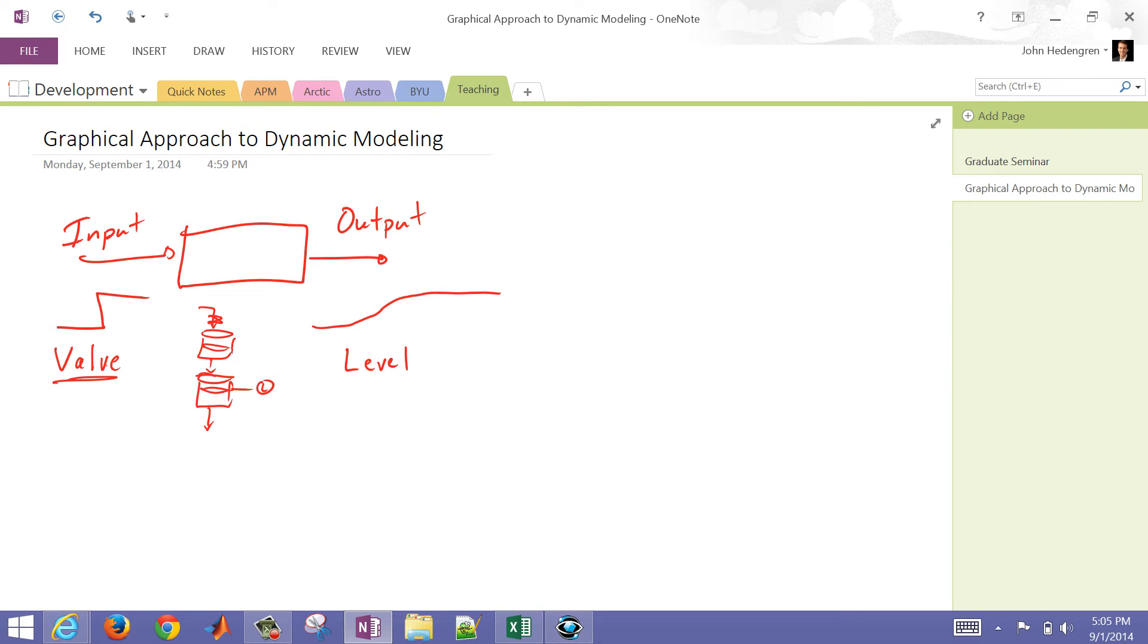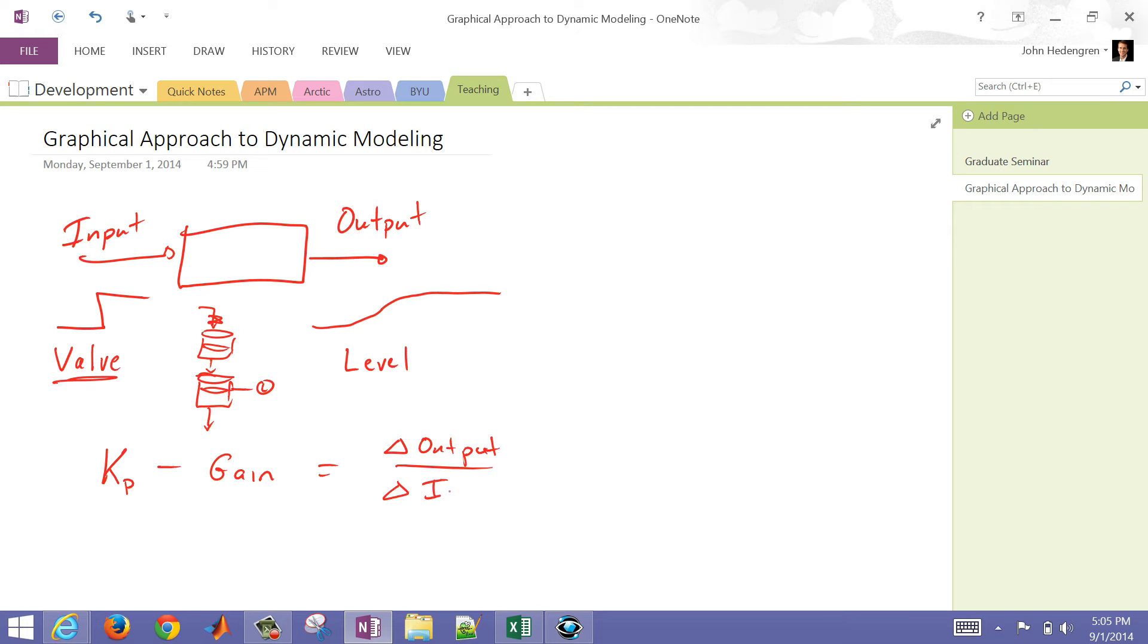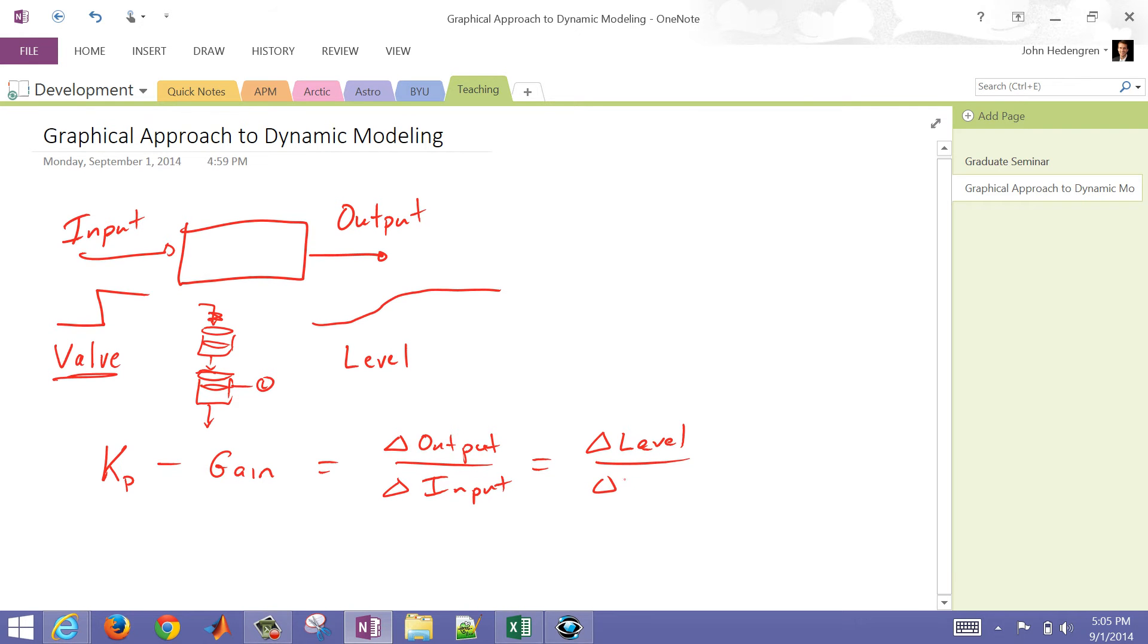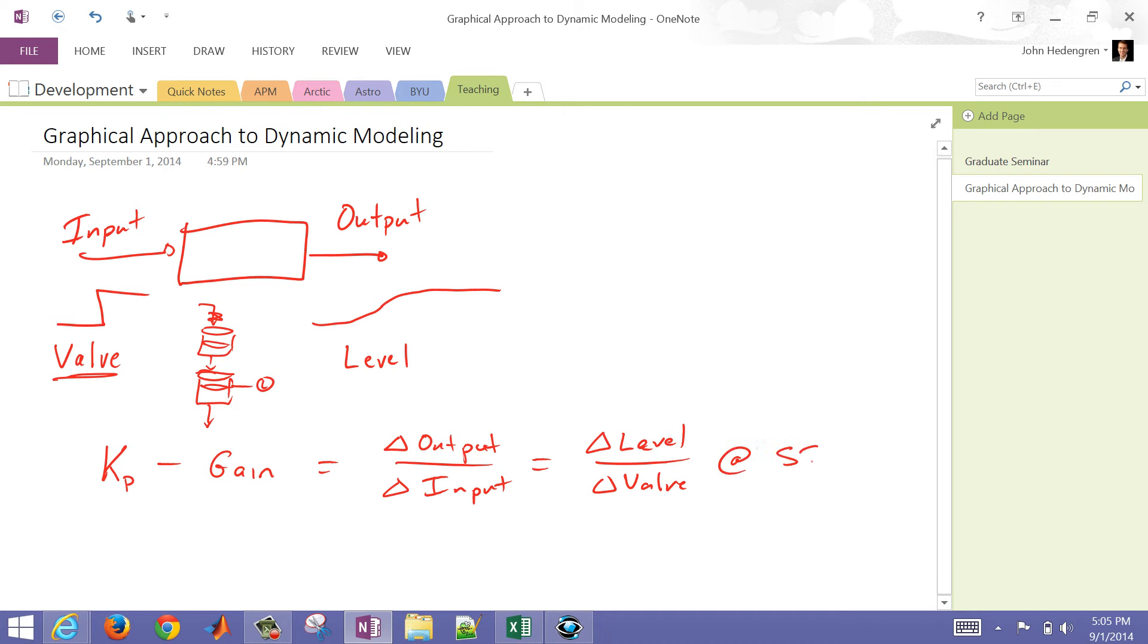We're going to use three constants. We're going to use Kp, and that's going to be our gain. That's going to be the delta output divided by the delta input. So in this case, it's going to be the change in the level over the change in the valve, and this is going to be at steady state. After a long period of time, when you have a change, you're going to look at the change before and after and look at the deltas.